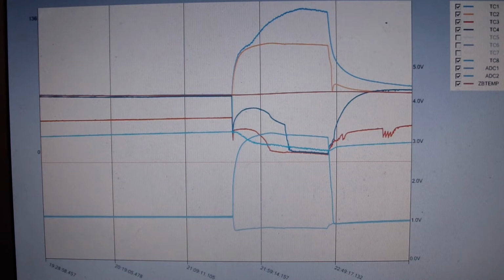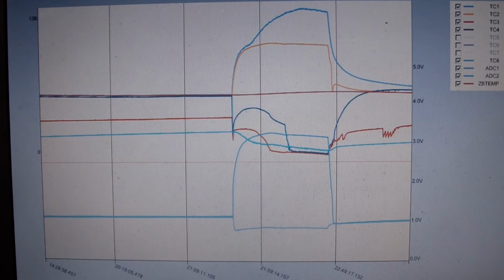Probably because the pressure drops so suddenly, the liquid that is in there starts to boil off quite rapidly and cools those thermocouples. Then you see a rather sudden rise again in the temperature of both of those, more noticeable in the one after the heat interchanger that's in the ambient environment here. Probably because, again, you have that capillary tube wrapped around it.